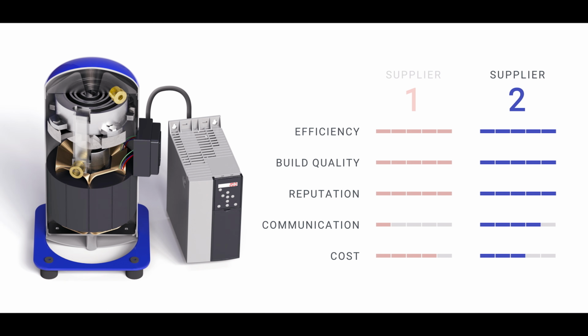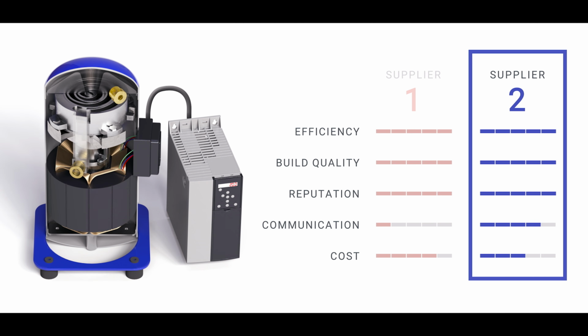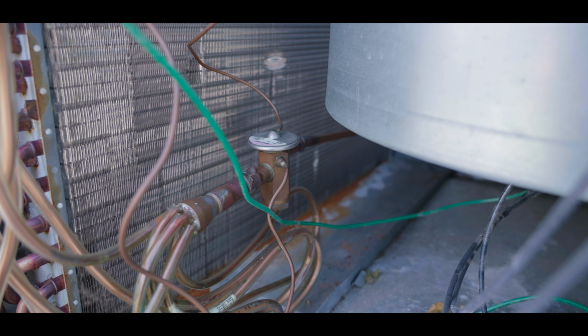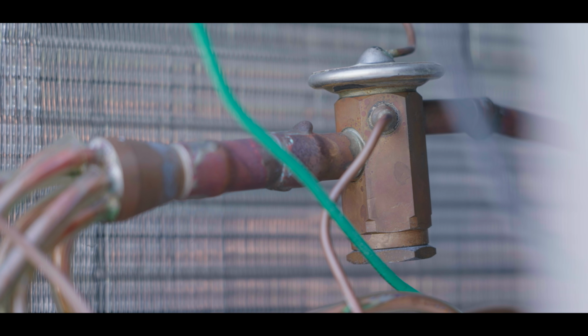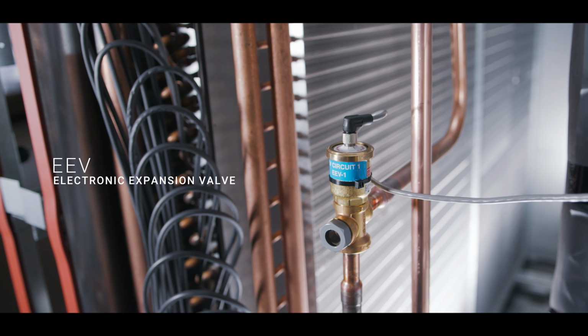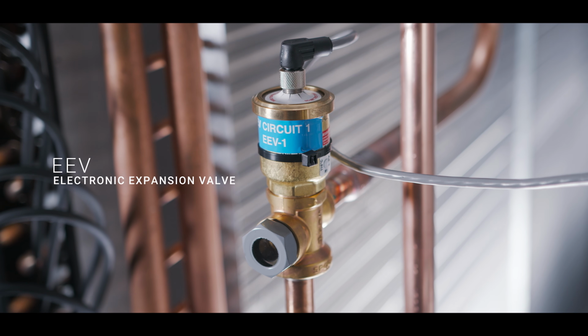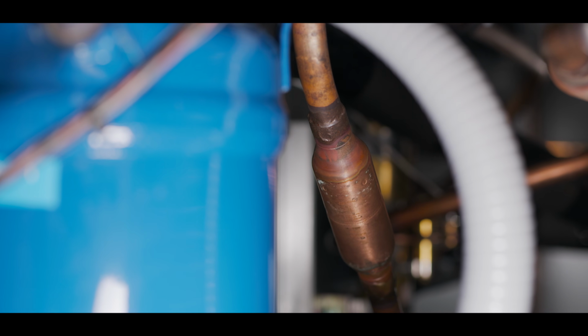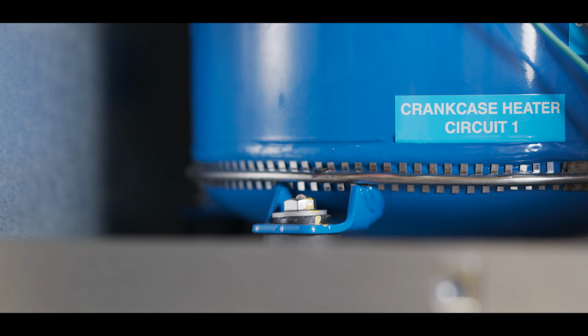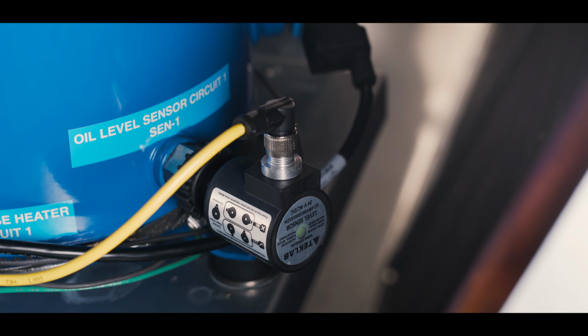So one of the first and most important decisions was deciding on that compressor. After that, some things came into better clarity. For example, we would have never used a TXV in place of an EEV. The EEV was almost mandated because of that variable speed compressor. Check valves in the system and accumulators, crankcase heaters, things like that—if we're going to go with this high quality compressor, we want to do everything possible to protect it.